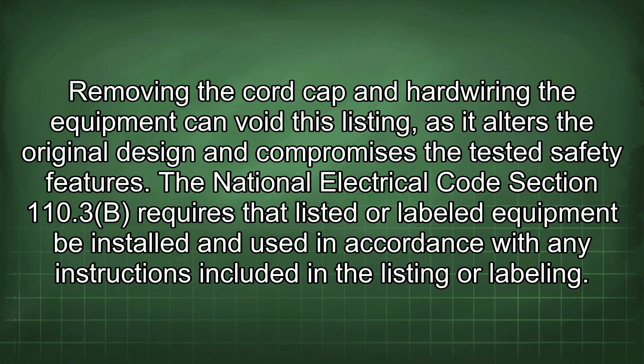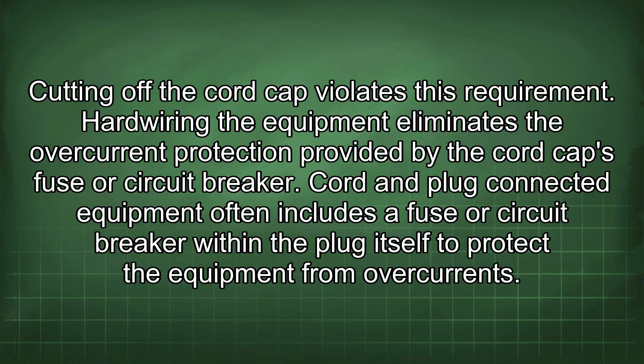Hardwiring the equipment eliminates the overcurrent protection provided by the cord cap's fuse or circuit breaker. Cord and plug connected equipment often includes a fuse or circuit breaker within the plug itself to protect the equipment from overcurrents. Hardwiring the equipment directly to the building's electrical system bypasses this protection. This increases the risk of damage to the equipment and potentially creates a fire hazard.